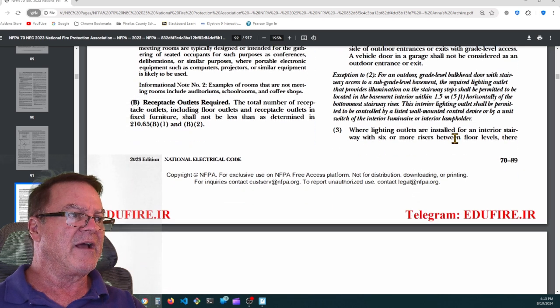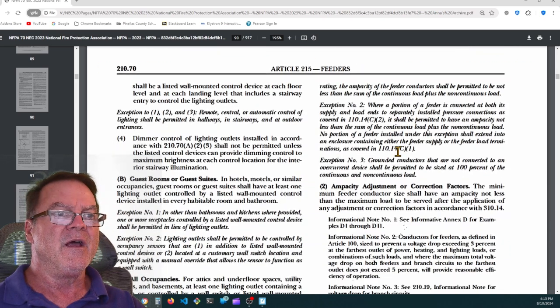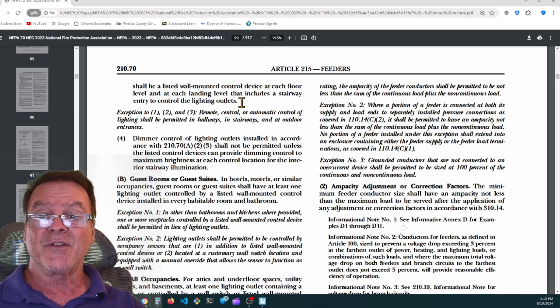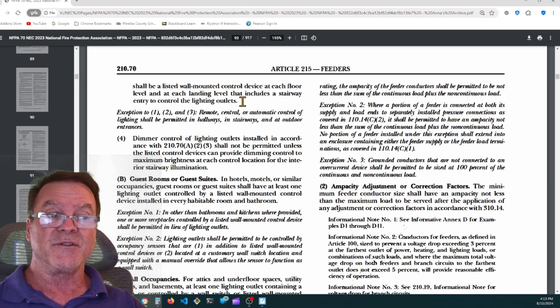And 3, where lighting outlets are installed for an interior stairway with 6 or more risers between floor levels, there shall be a listed wall-mounted control device at each floor level and at each landing level that includes a stairway entry to control the lighting outlets. So that's the 3-way switches we were just talking about. Stairways have to have 3-way and 4-way switches depending on how many landings that stairwell has.